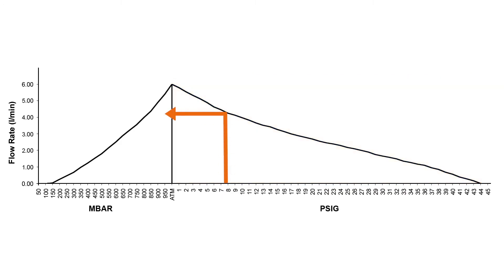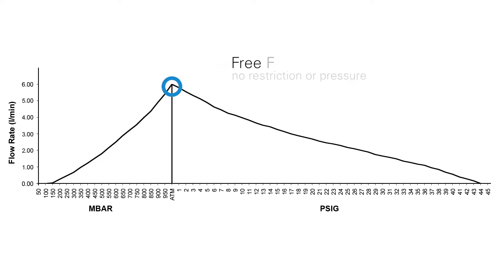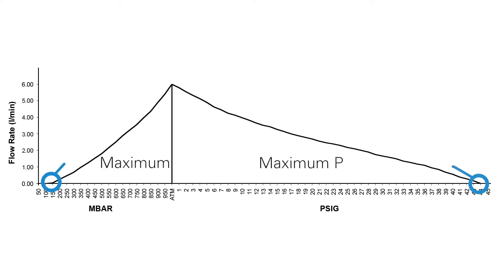The pump's performance, known as flow rate, is measured in liters per minute. Regardless of the units, your interpretation of the flow curve will be the same. The point in the middle where the two curves meet is the pump's free flow or maximum flow, meaning there is no restriction or pressure on either side of the pump. The endpoints of the curves represent the maximum vacuum or maximum pressure capabilities of the pump, where the flow rate has dropped to 0 liters per minute.